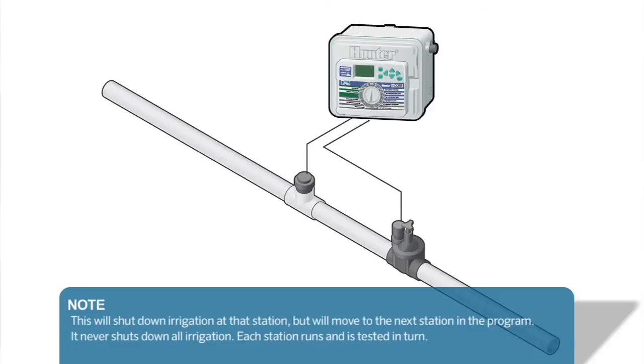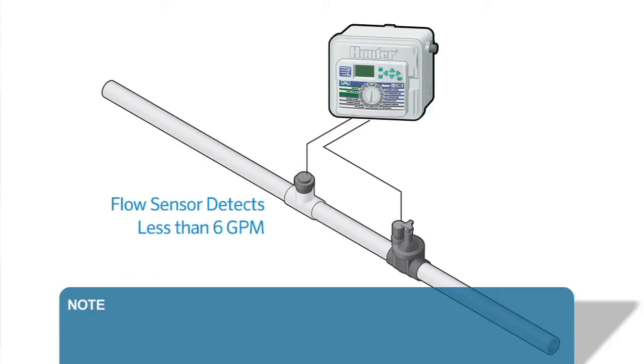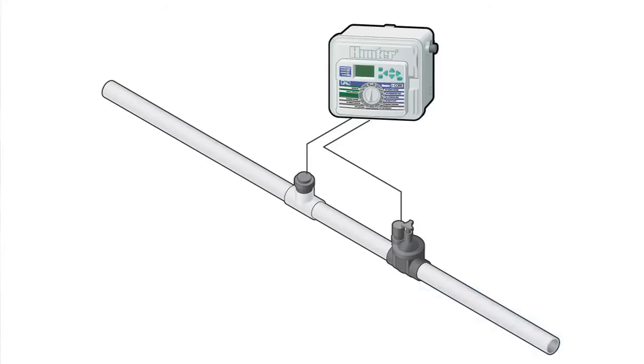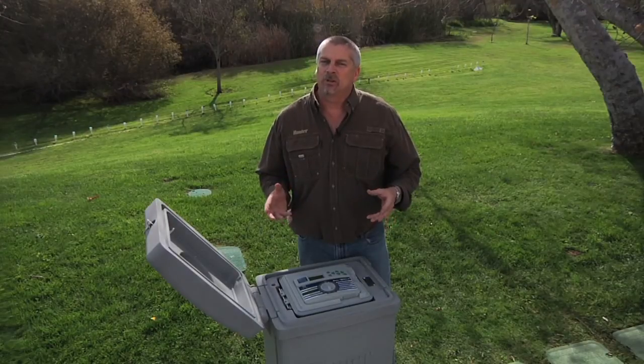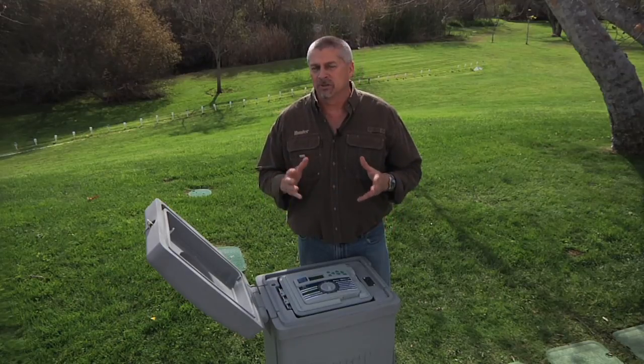The same principle applies to underflows. If the sensor detects a flow of less than 6 gallons per minute due to a valve not opening, then it will shut down, wait a minute, and then restart the station. The controller would then show an underflow alarm because the system is running 50% under the expected flow. Again, you can change the limits at which an overflow or underflow occurs per station.